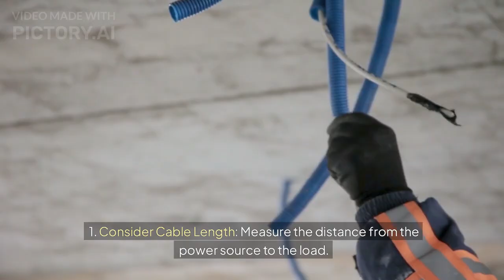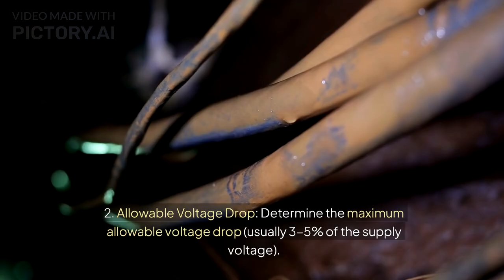3. Consider cable length. Measure the distance from the power source to the load. 4. Allowable voltage drop. Determine the maximum allowable voltage drop, usually 3 to 5% of the supply voltage. 5. Select cable material. Choose the conductor material, for example, copper or aluminum, and check its resistivity.